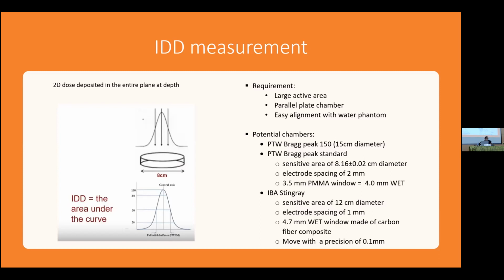The water phantom, because as standard we do measurements in water. And the reason you want liquid water as opposed to maybe some plastic or anything is because you're going to be moving this to take measurements at different points along this curve, to be able to ensure the characteristics of the beam as described is what you're actually measuring.